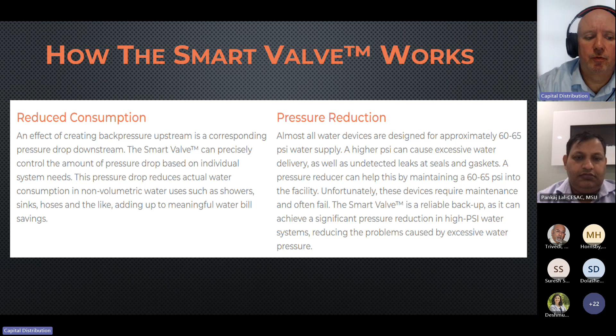And on top of that, this can actually be a secondary pressure reducing valve, in the sense that you will get a drop in pressure depending on where you set it. It could be very minimal, or on the larger sizes, you can almost shut the water off, which I'll show in a minute. Because of that, if the pressure is high coming into your home or your property, you're getting it to that range where it should be, which is that 60 to 65 recommended range, to ensure that you're not doing any damage to your fixtures.